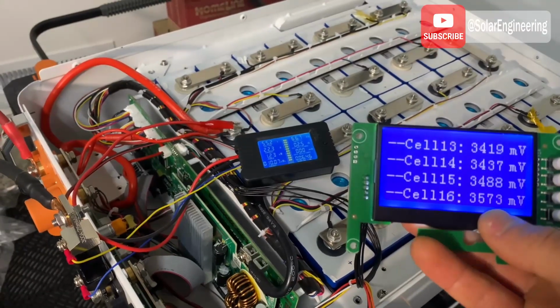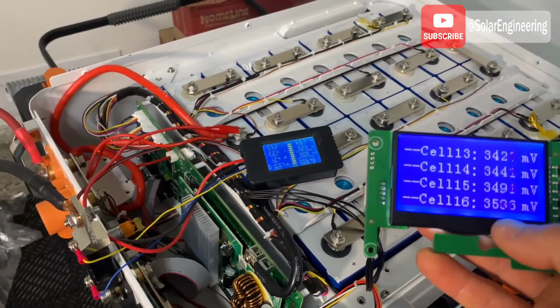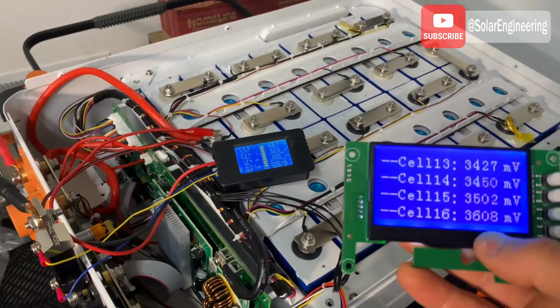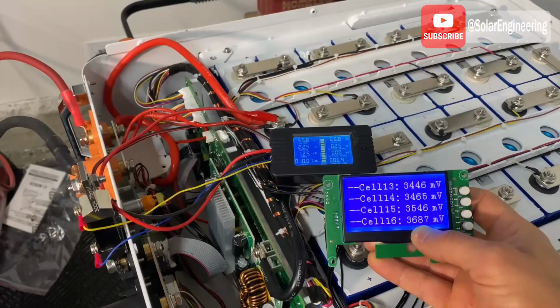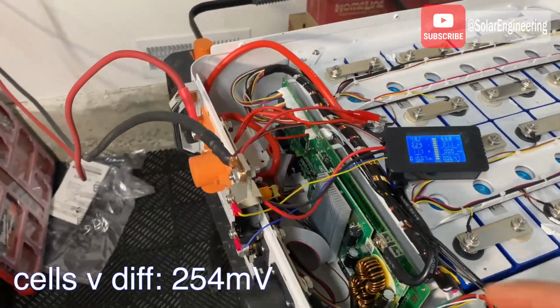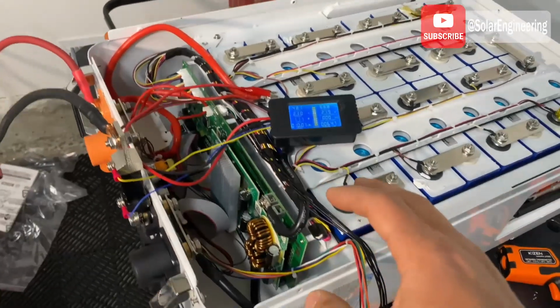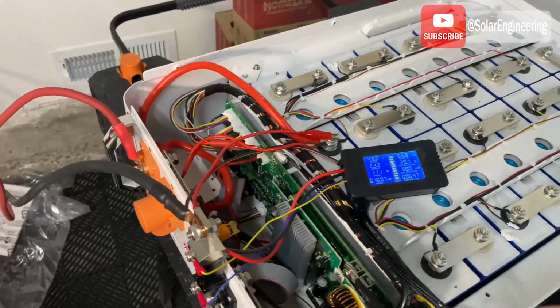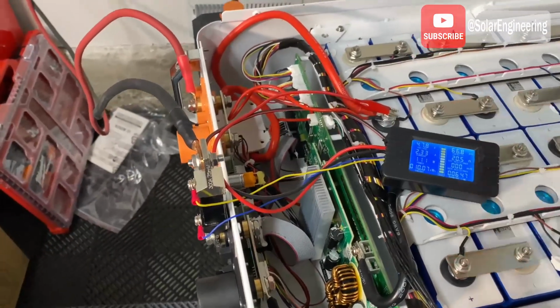I guess cell number 16 will first reach 3.7 volts, which is the disconnect voltage in the BMS for this pack. Reaching 3.7 volts and 55.9 volts on this pack, you may hear this click - the relay disconnected the battery from the inverter. Now I'm going to reset this meter and we'll do the capacity test.